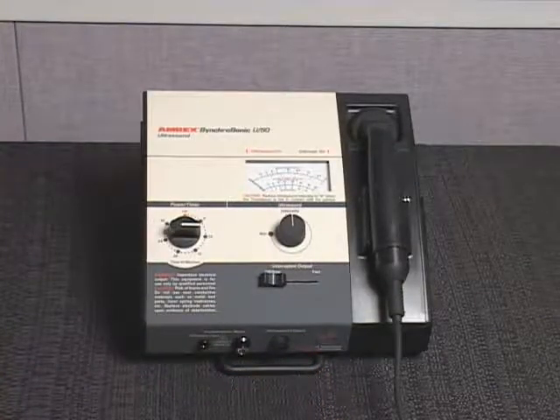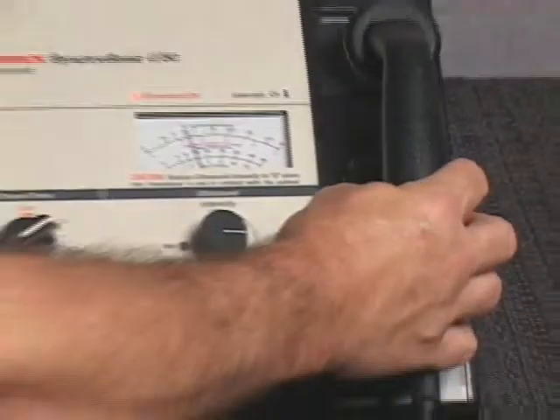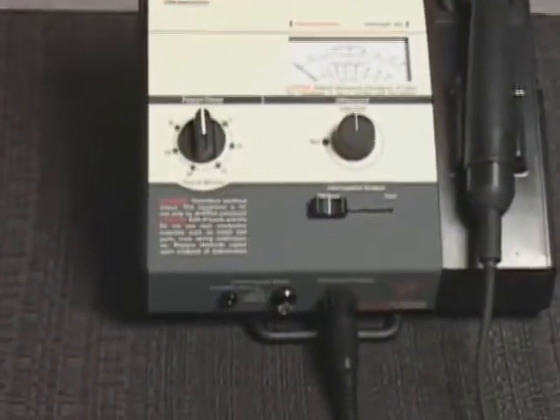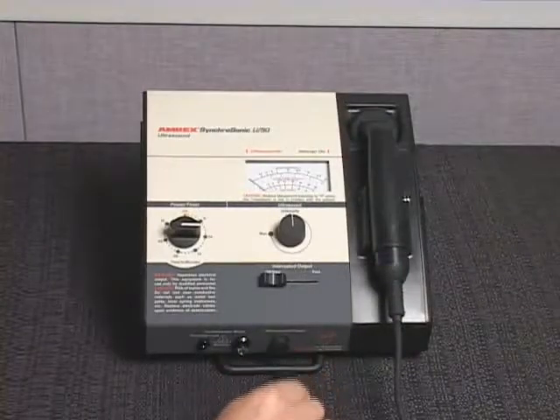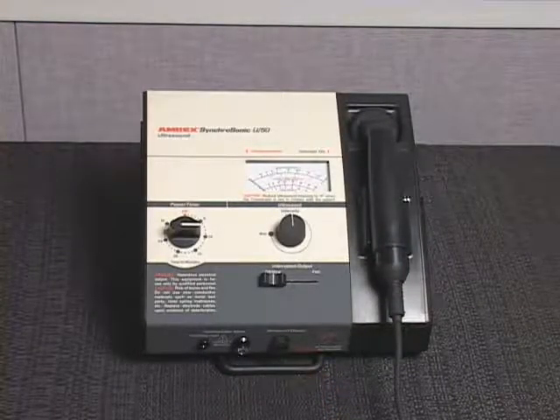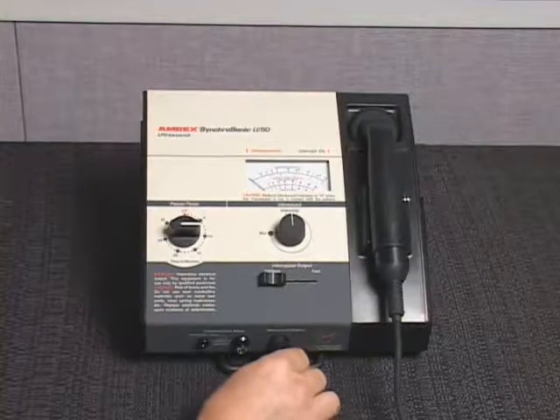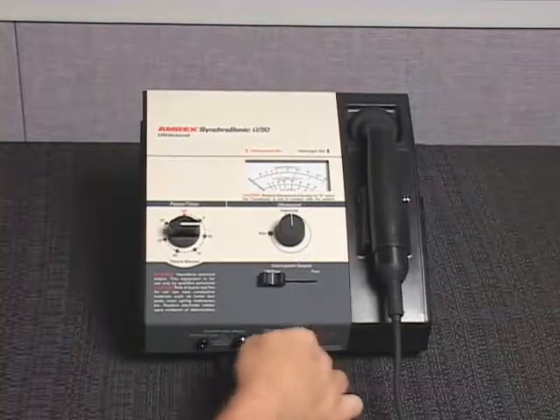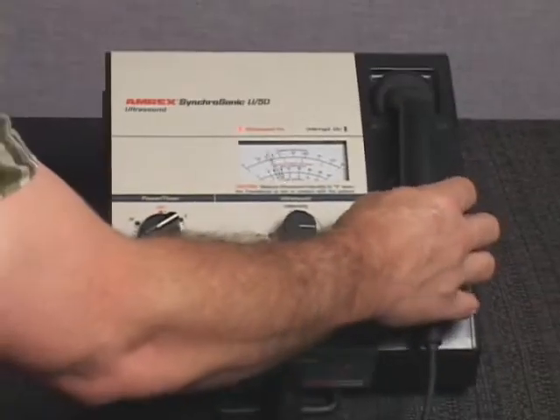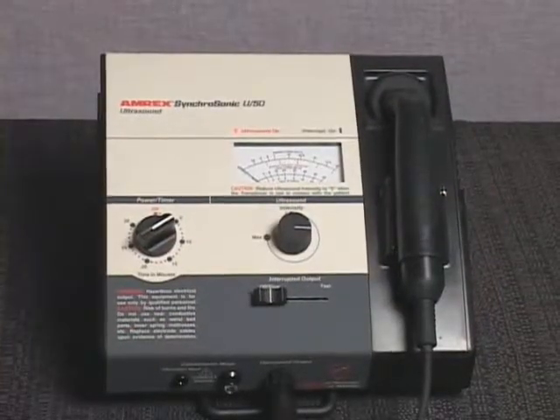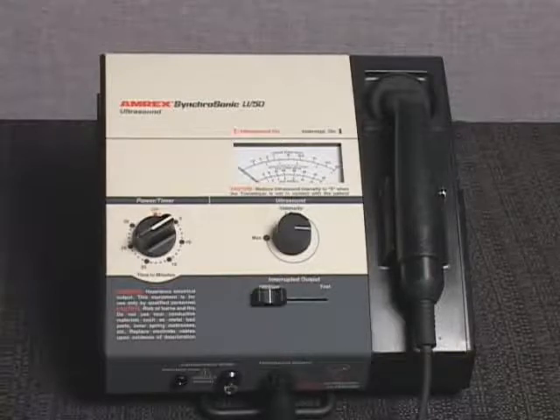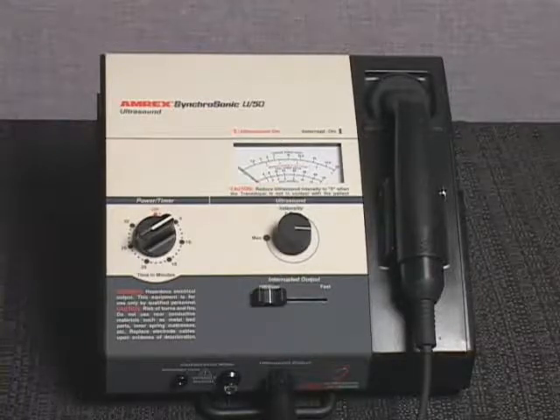The U50 is equipped with a cable fault alarm system, transducer protection switch, interrupted output, and has combination therapy capability. The cable fault alarm system will alert the user to transducer cable damage or improper cable connection by activating an audible and visible alarm. The transducer protection switch, located on the transducer cradle, will shut off ultrasound output from the transducer when the transducer handle is placed in the cradle during treatment.